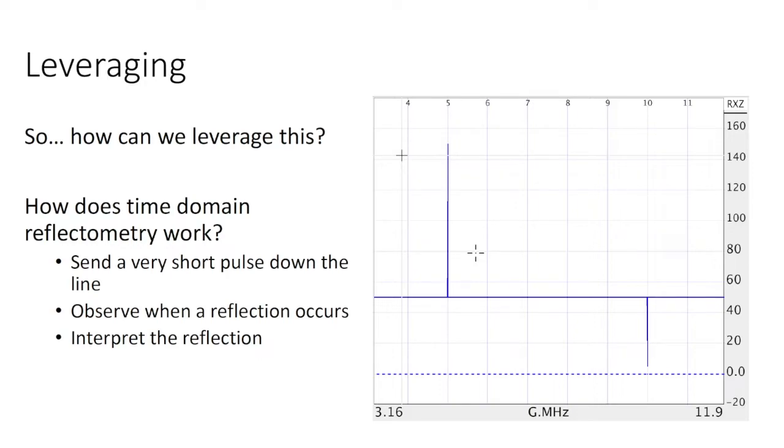Now, if the circuit is perfectly matched, there would be no reflection. If the circuit has a place where there is a lower impedance than the transmission line, for example, there will be a negative going pulse. And if there's a place in the circuit with a higher than Z-naught impedance, there would be a positive going pulse.